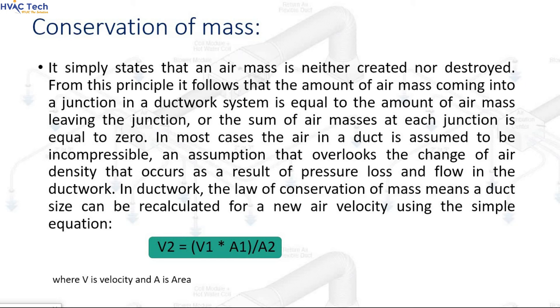Conservation of mass simply states that an air mass is neither created nor destroyed. From this principle, it follows that the amount of air mass coming into a junction in a ductwork system is equal to the amount of air mass leaving the junction, or the sum of air masses at each junction is equal to zero. In most cases the air in a duct is assumed to be incompressible. In ductwork, the law of conservation of mass means a duct size can be recalculated for a new air velocity using the simple equation: V2 = V1 × A1 / A2, where V is velocity and A is area.